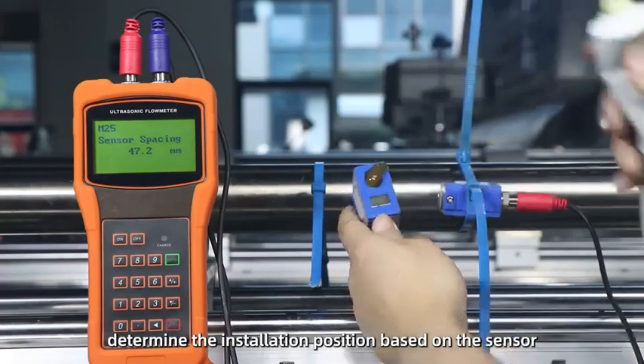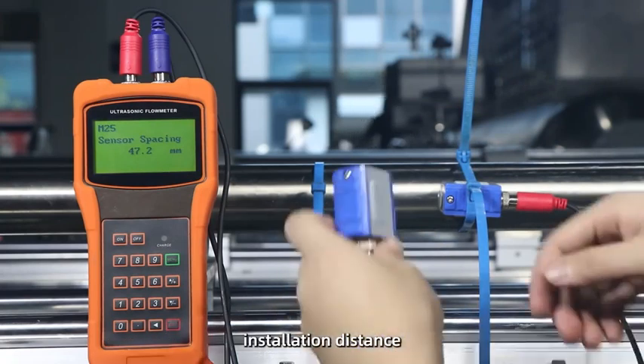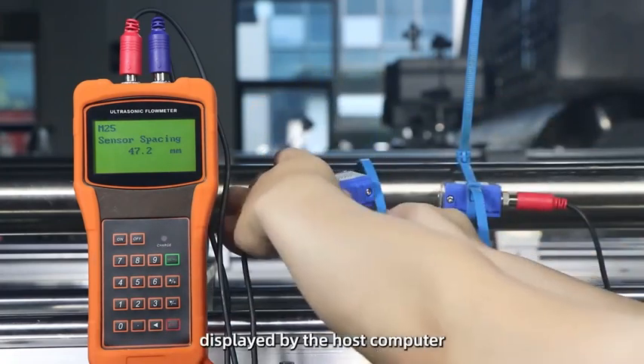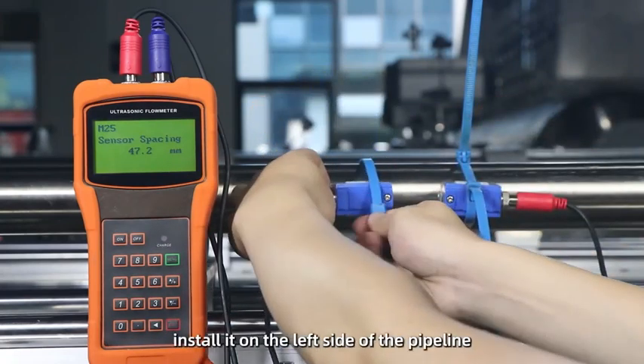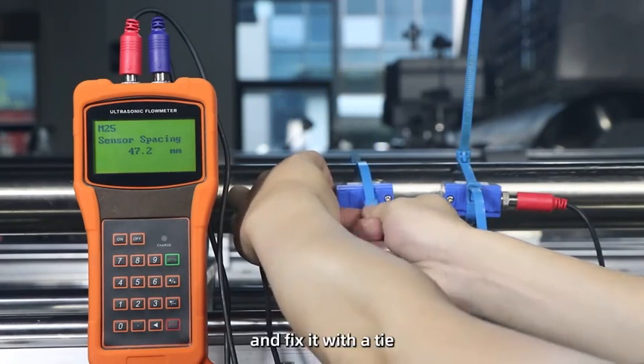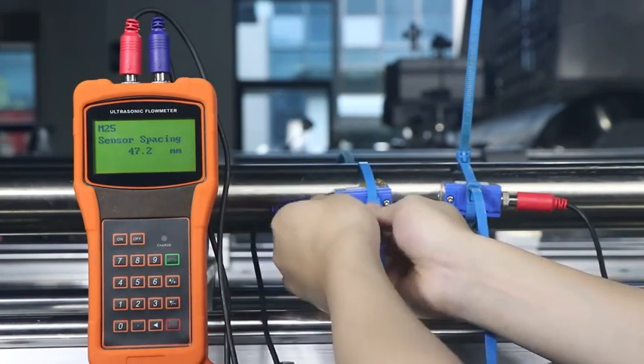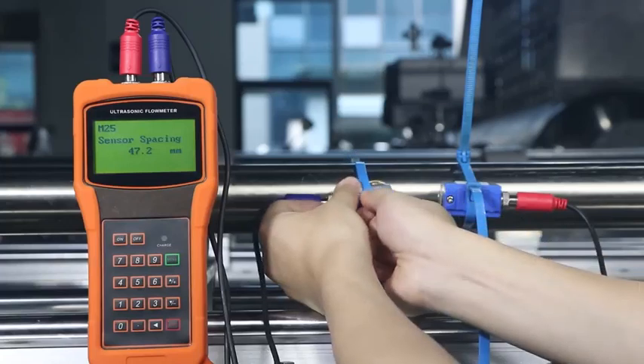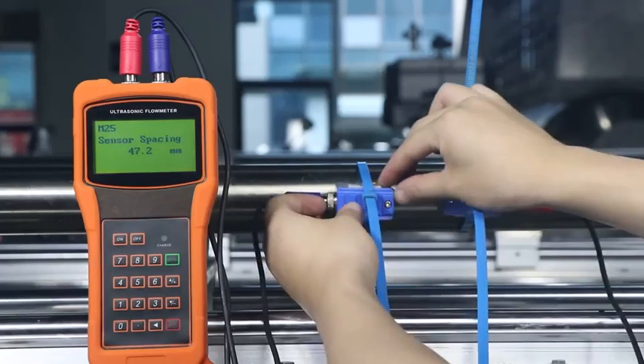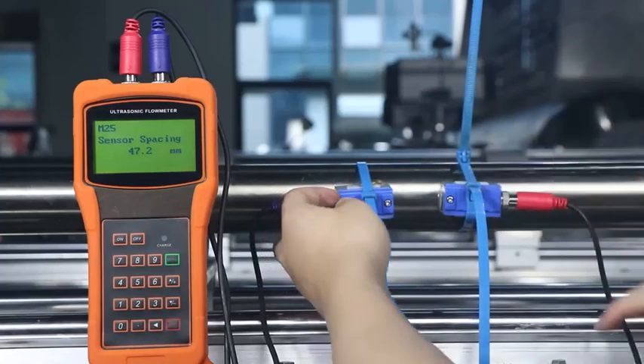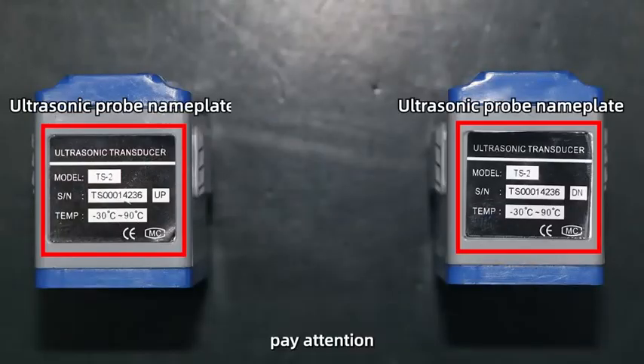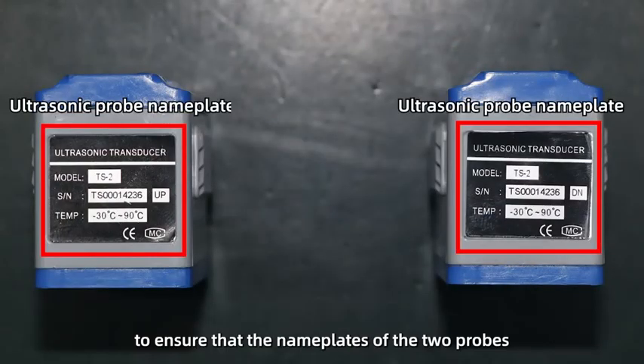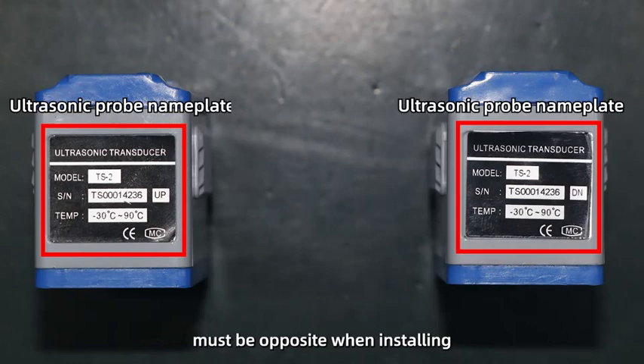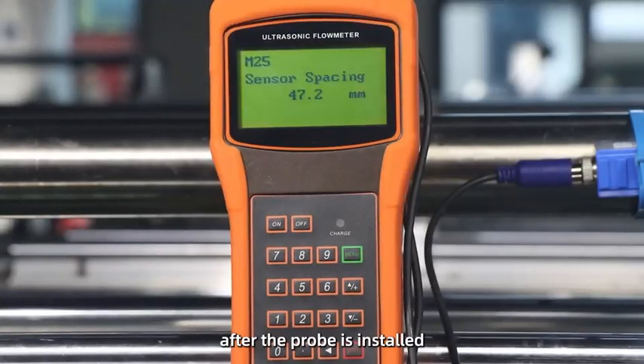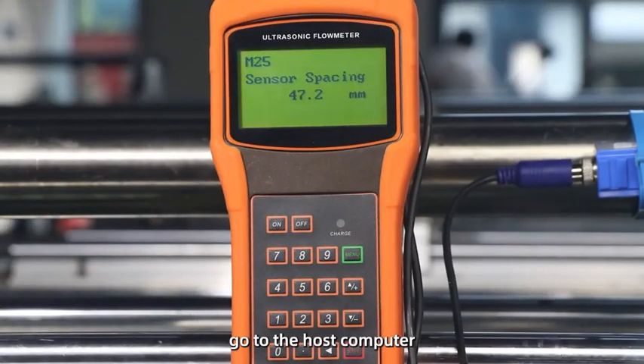Determine the installation position based on the sensor installation distance displayed by the host computer. Install it on the left side of the pipeline and fix it with a tie. Pay attention to ensure that the nameplates of the two probes must be opposite when installing. After the probe is installed, go to the host computer to check whether it is installed correctly.